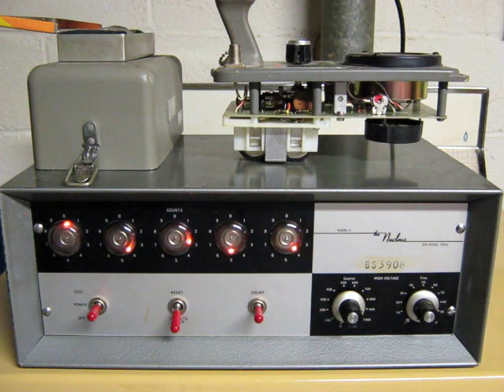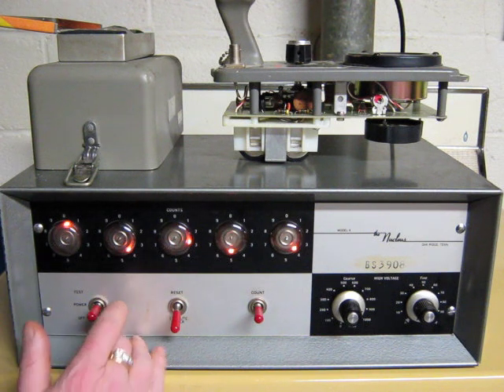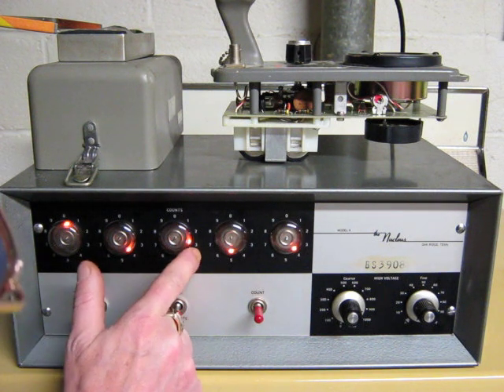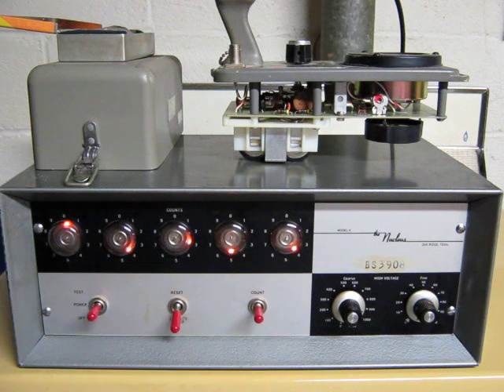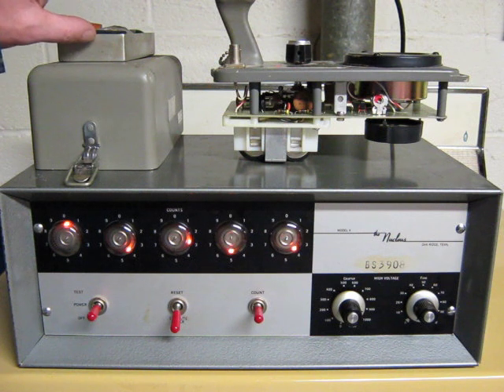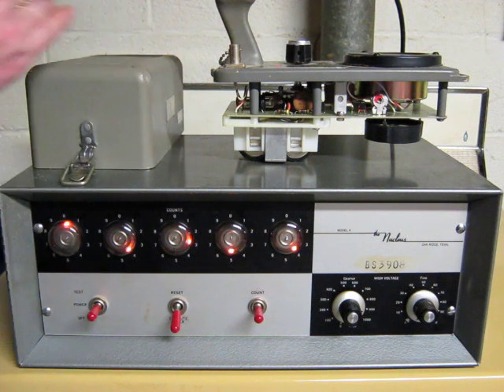Okay, that 1 minute, it stopped counting. The counts are 4, 3, 5, 4. So 4,354 counts per minute. That's the probe this far away from this sample, and whatever else is in this box. Not horrible, but it's pretty repeatable.